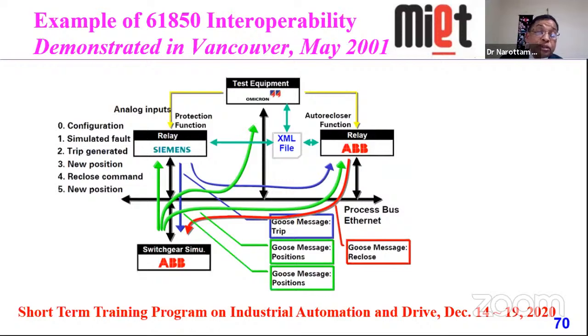They defined: 0 is configuration, 1 is simulated fault, 2 is trip generated, 3 is new position, recloser command, and new position. ABB did the simulation switching, and their system connected with Siemens relay and ABB relay, with Omicron test equipment. I have good correspondence with Omicron, since they provide equipment support for testing IEC 61850, CMC, and other types. In this case the GOOSE message syncs trip and position.